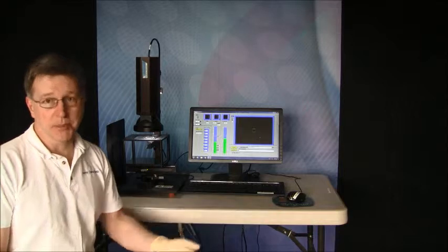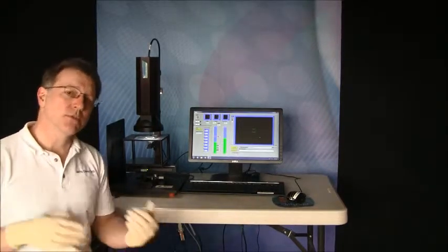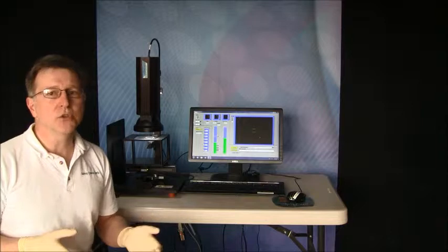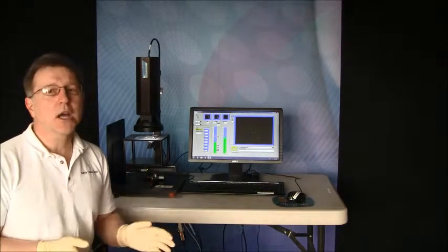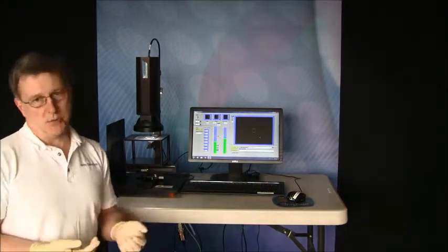So I've always envisioned the Savvy Inspector as a tool to be used by optics manufacturers for inspection prior to shipment. But an increasing number of Savvy Inspectors are actually being used on incoming inspection. And that's a whole different kind of problem if you think about it. A lot of times when you're on the receiving end of a component, what you need to do is be able to properly document incoming optics that don't meet spec in a way that your vendor can understand and take action on. So the Savvy Inspector is a useful tool for that, and let me show you how that would work.